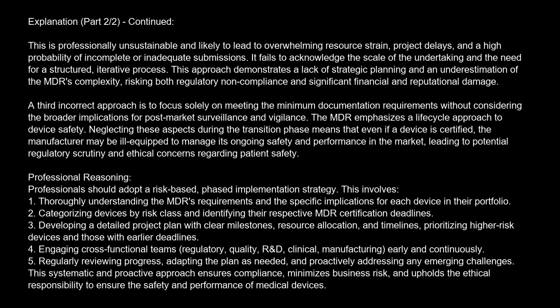A third incorrect approach is to focus solely on meeting the minimum documentation requirements without considering the broader implications for post-market surveillance and vigilance. The MDR emphasizes a life-cycle approach to device safety. Neglecting these aspects during the transition phase means that even if a device is certified, the manufacturer may be ill-equipped to manage its ongoing safety and performance in the market, leading to potential regulatory scrutiny and ethical concerns regarding patient safety. Professional reasoning. Professionals should adopt a risk-based phased implementation strategy.